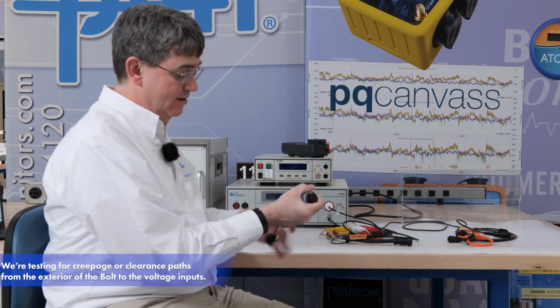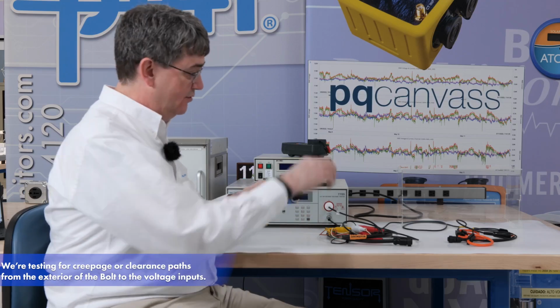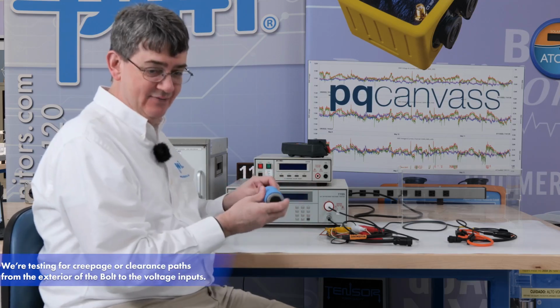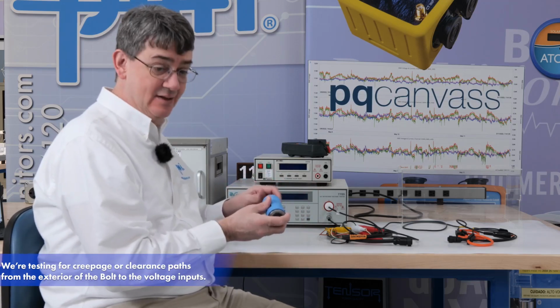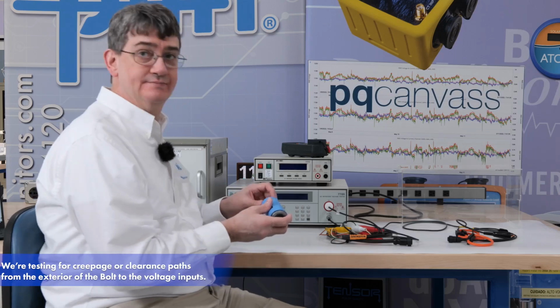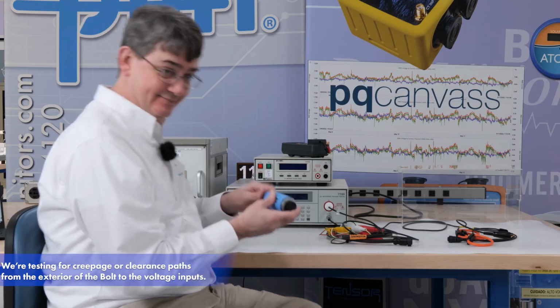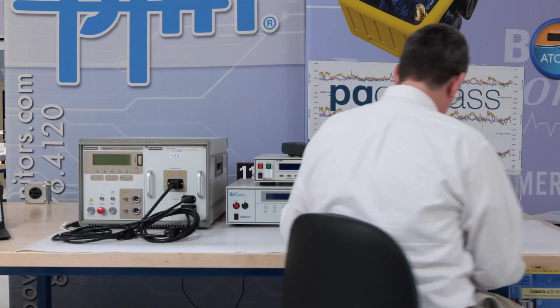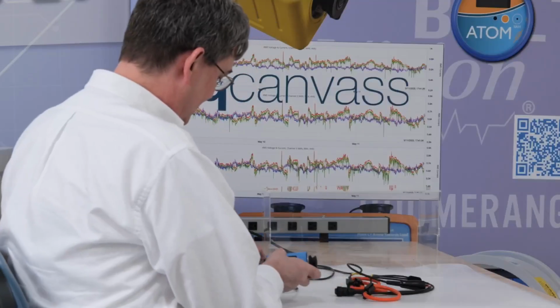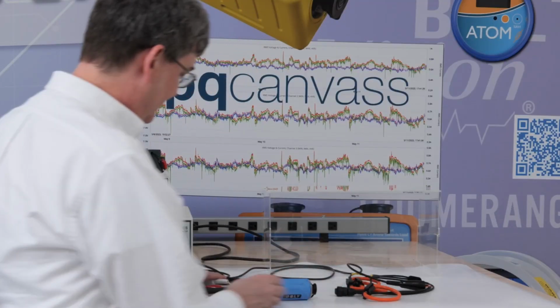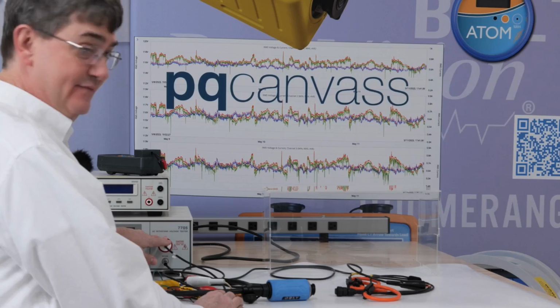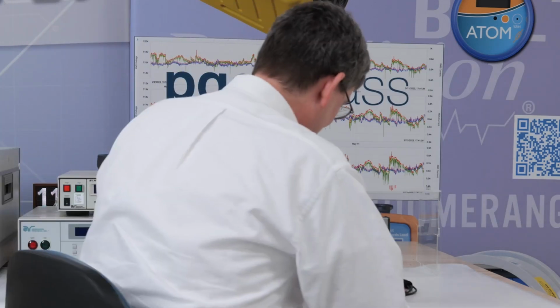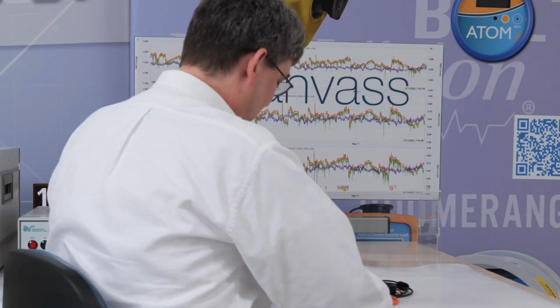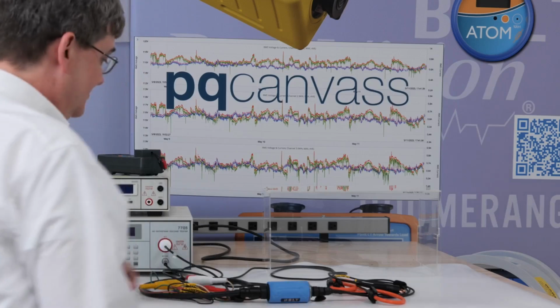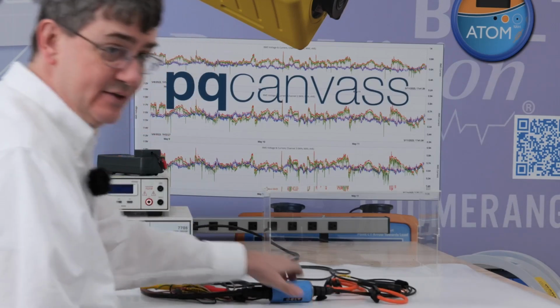If you're holding the bolt while an impulsive transient occurs, or you're holding the CTs, we want to make sure it's safe. And this is a test that you also will perform on the bolt. So let's check it out. We'll connect the voltage front end, and here we have all the voltage inputs tied together to the hot side of the Hipot tester, and on the other side we have the CTs. And to simulate a person's hand, we are going to use copper foil tape.